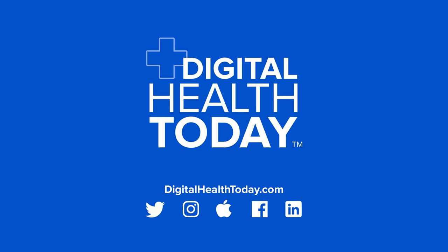However, the device itself needs to have all the smarts and it needs to have a basic ability to communicate any error conditions, any alarms, or any time the person is unsafe, and therefore they need to be designed together. This is why you can't just build a pump, lock it down, build an app, and put them together. The device needs to be designed in the context of the phone being present most of the time, not present some of the time, and sometimes that device needs to be the primary interface. But you need to have a sharing of responsibilities across an architecture that distributes intelligence. This is a system rather than a device or a component.